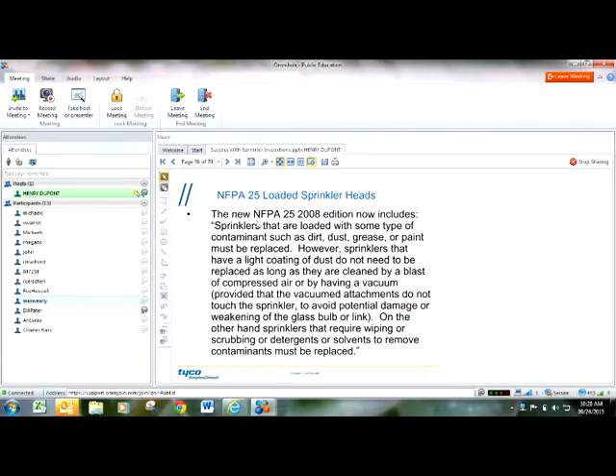The 2008 edition of NFPA 25 came out and said that before this edition, NFPA just plainly said that you cannot clean sprinkler heads. There's just no way to clean them whatsoever. Well, the 2008 edition came out and said that you can clean sprinkler heads as long as you can do it by a blast of compressed air, or you can vacuum the contaminants off of it. It does go on to say if it requires any kind of scrubbing, wiping, or detergent, the sprinkler head shall be replaced.